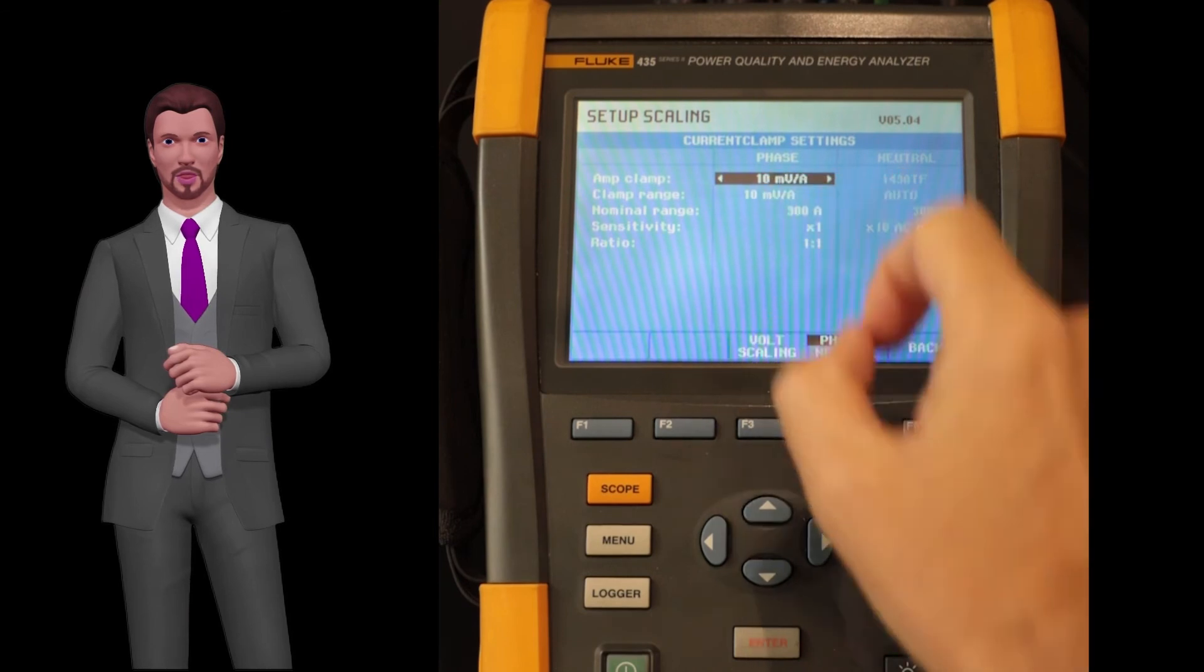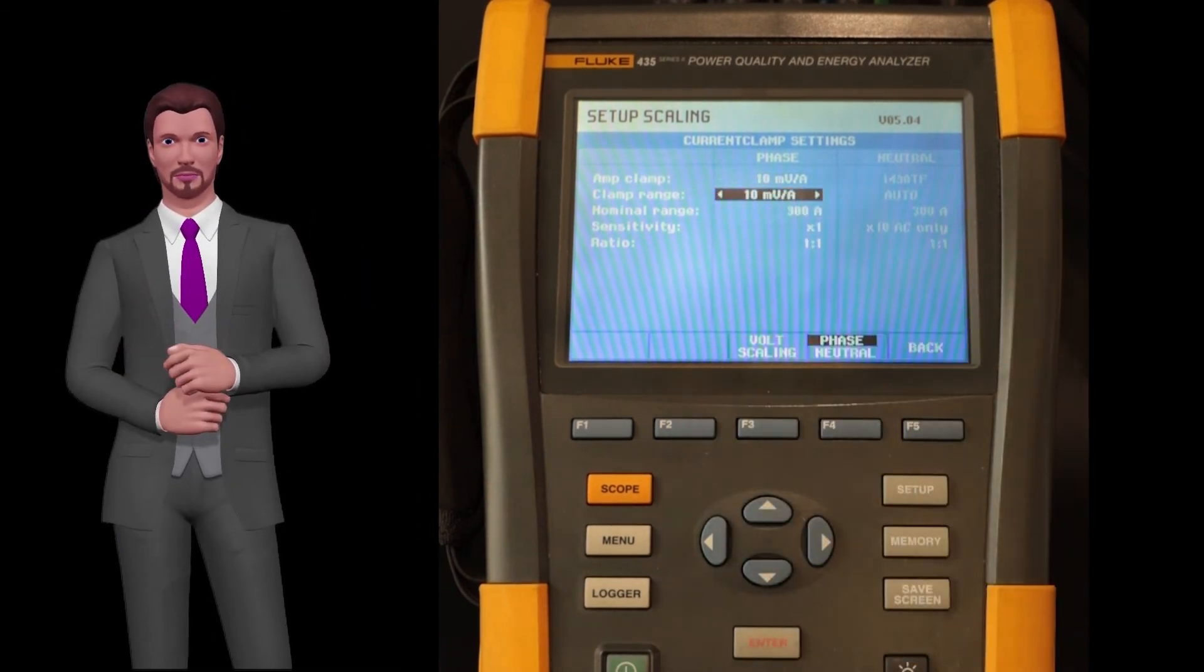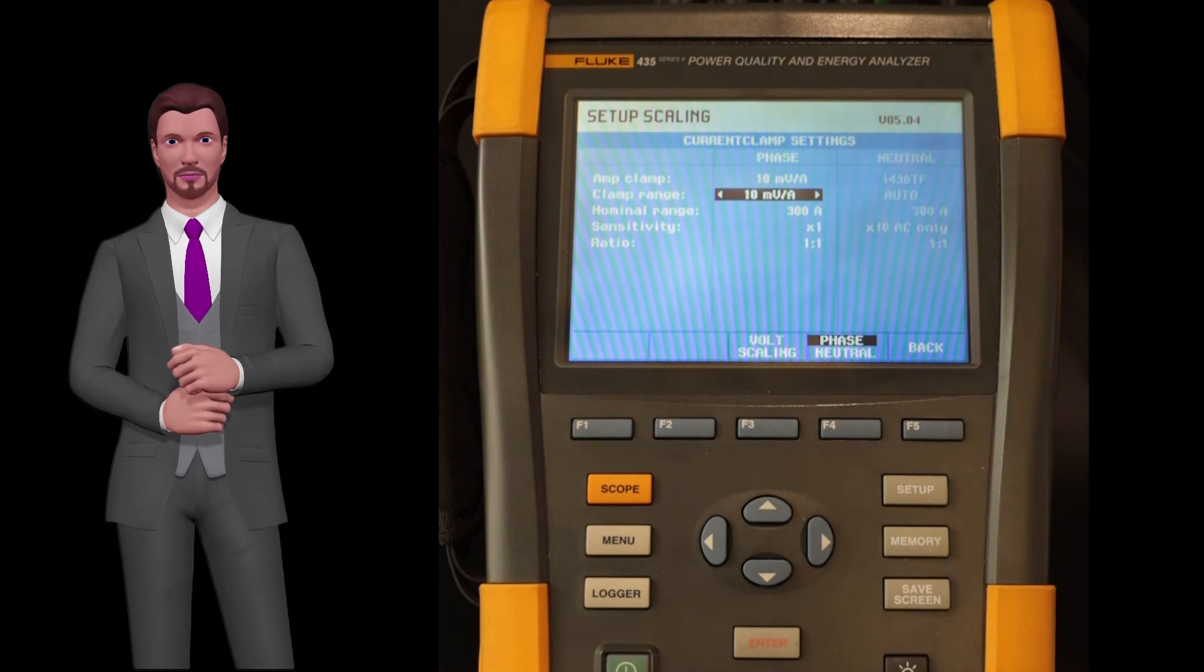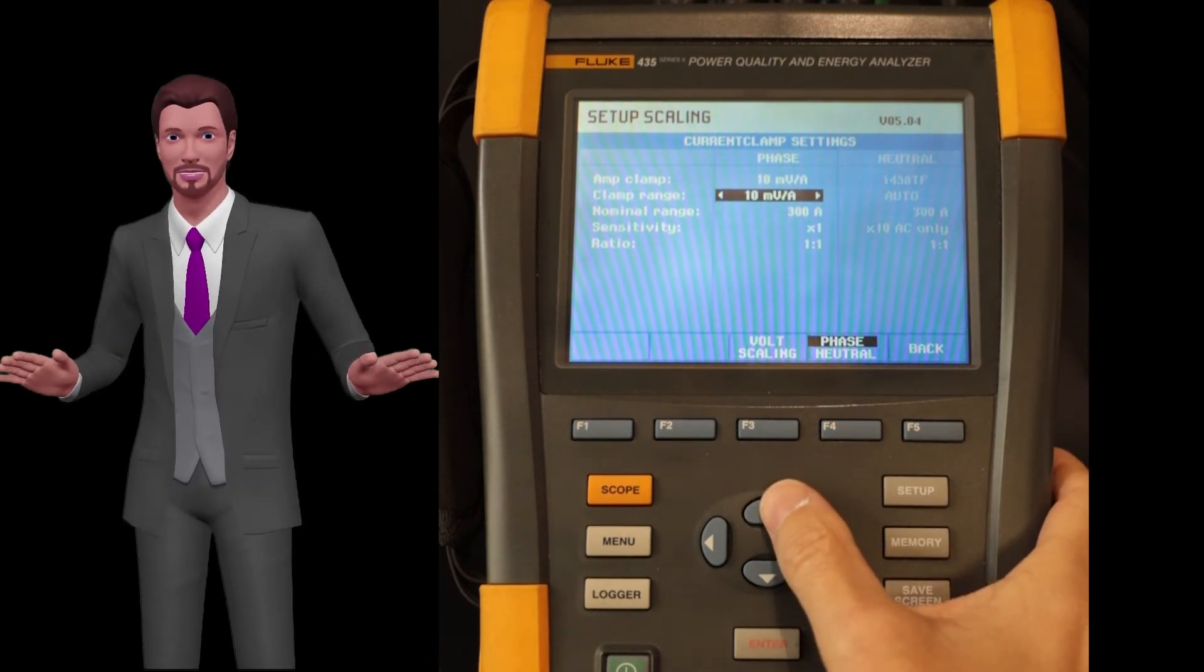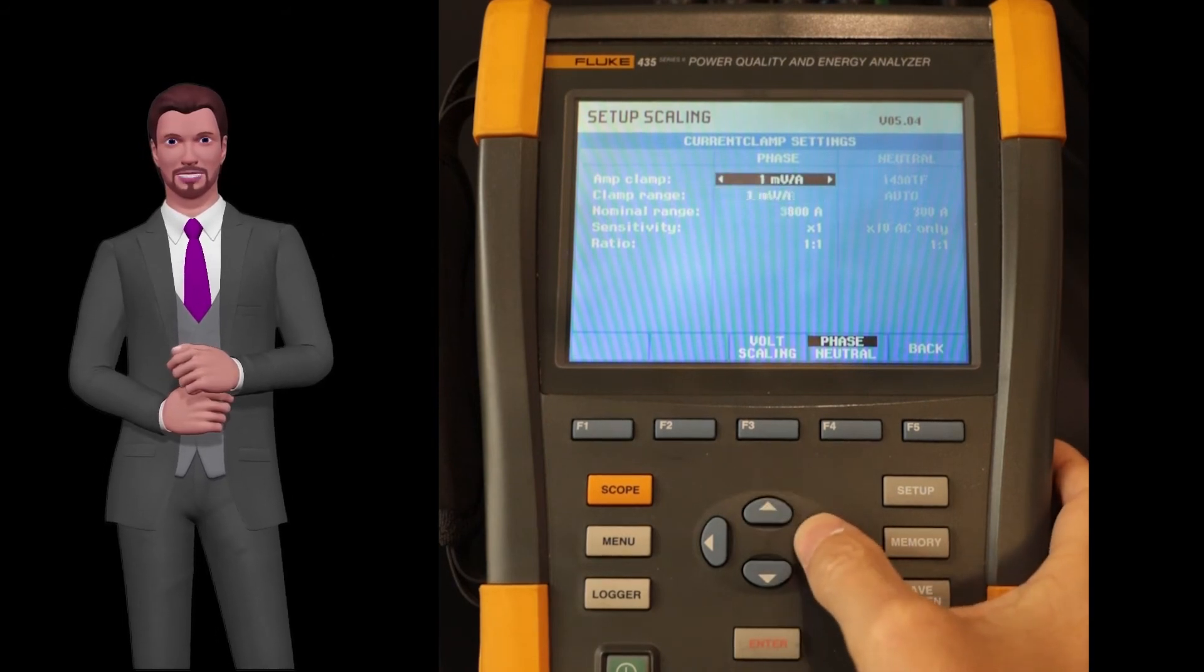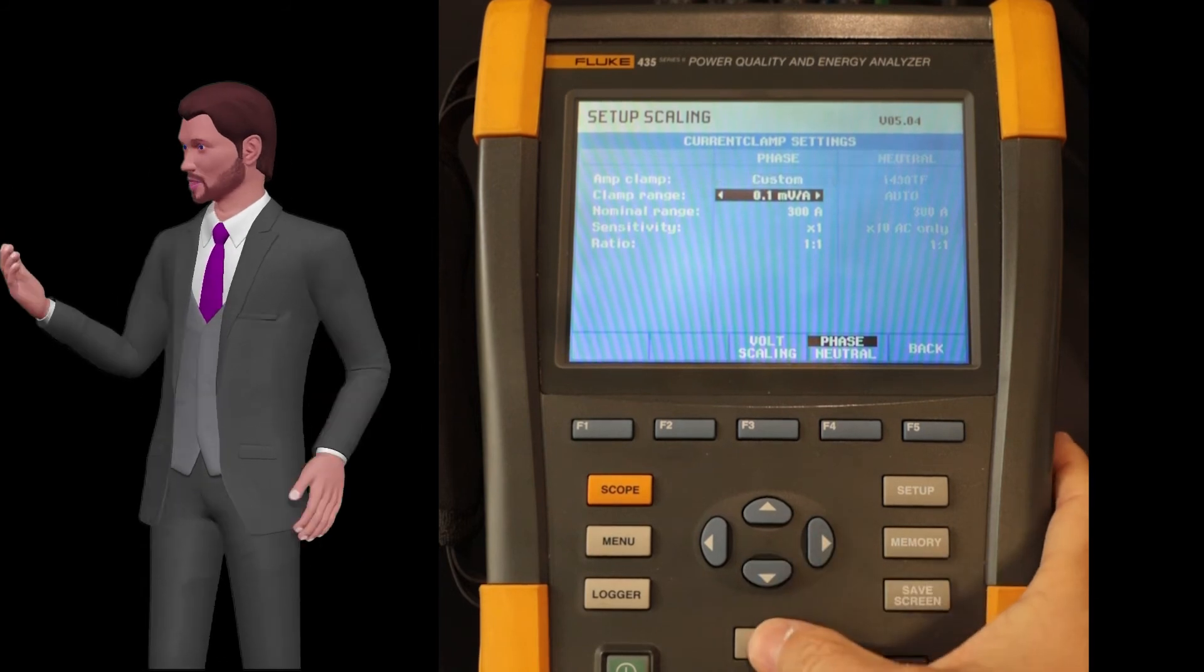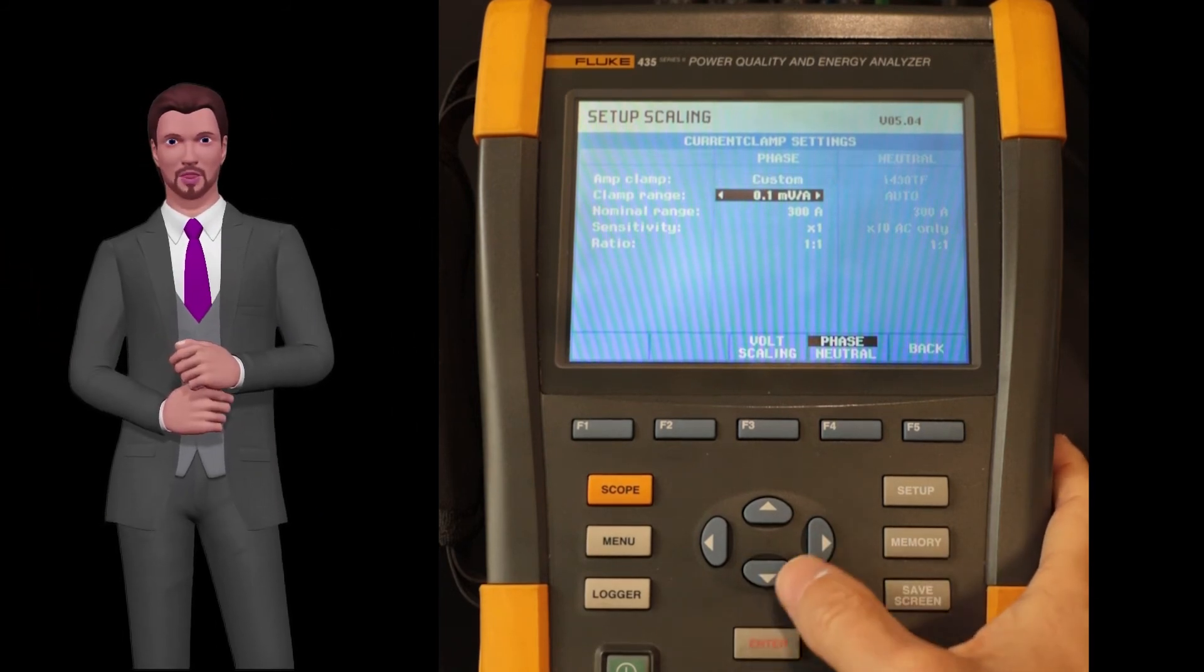In this case, precisely in the next parameter called clamp range, this value of millivolts per ampere will appear. In the case of using a special probe, the unit also allows to manually define the output of that probe. In this case we choose custom in the probe type, and now we can manually change the millivolts per ampere according to the technical specification of that probe.